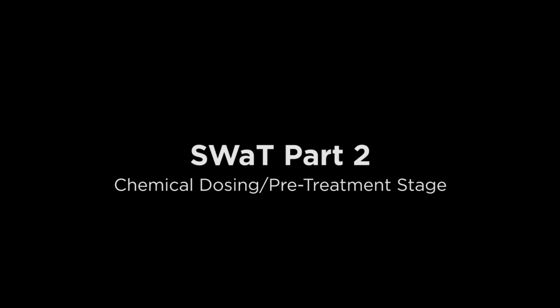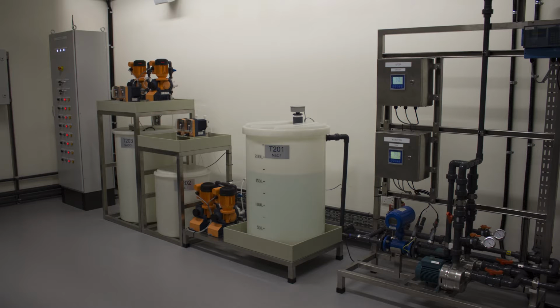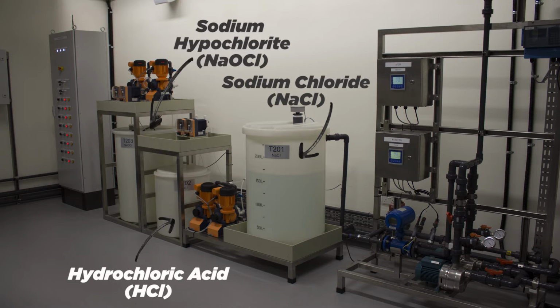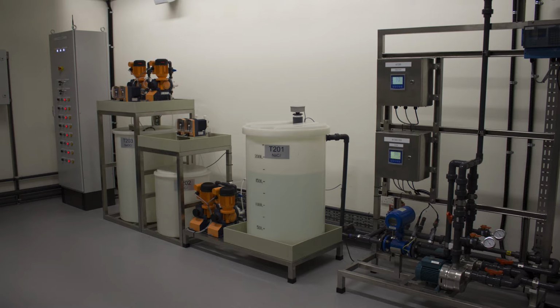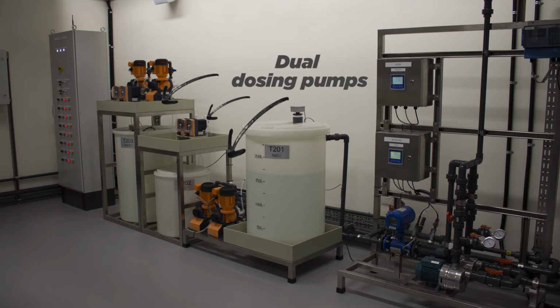We are now at stage 2 of SWaT, the chemical dosing or the pre-treatment stage. The controller in stage 2 is responsible for adding an appropriate amount of 3 chemicals to the water: hydrochloric acid, HCl, sodium chloride, NaCl, and sodium hypochlorite, NaOCl, for disinfection and pH and ORP balancing. These 3 sets of dual dosing pumps are controlled by the PLC at stage 2.